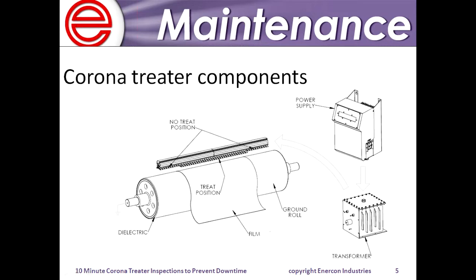What that does is convert that to a high frequency AC output, which goes down to the high voltage transformer. That transformer takes the high frequency signal source from the power supply and steps it up to 10,000 volts, that high frequency, high current, low voltage output, stepped up to 10,000 volts, which is brought to the potential of the electrodes, shown above the ground roll in the picture.